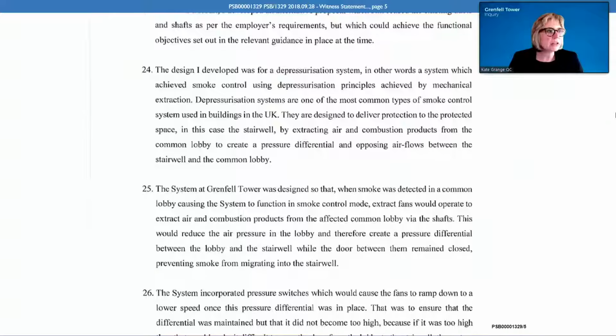So just pausing there, you say it's not a depressurization system. Do you accept that by having mechanical extraction through the lobby vents, north and south shafts, you would by definition be depressurizing the lobby? Do you accept that? You are, but because the industry has a specific definition for depressurization in 12101 part 6, use of that term would mislead the reader to believe that it is one of those systems.